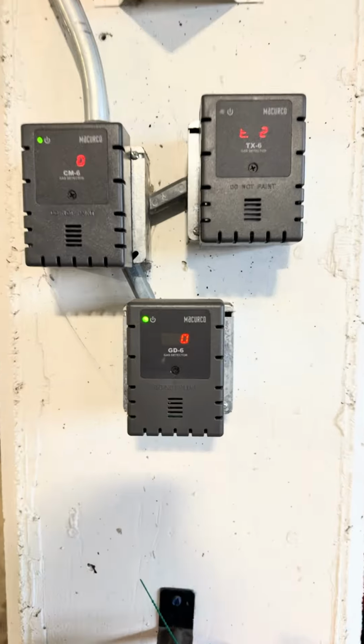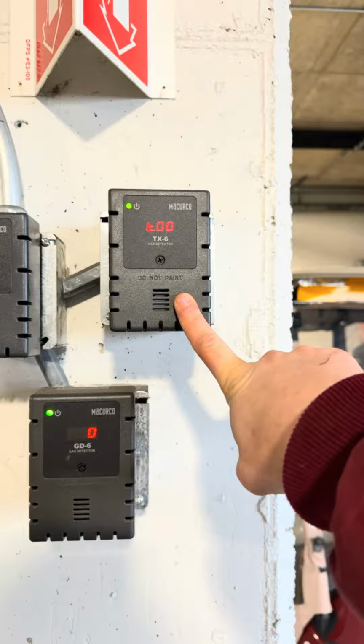When they've passed their shelf life, you're going to get that error code. We're supervising 3 gases in here: methane gas, CO gas, and nitrogen dioxide gas. I'm going to show you guys how to replace the nitrogen dioxide sensor, and then how to calibrate it and test it. So let's go.